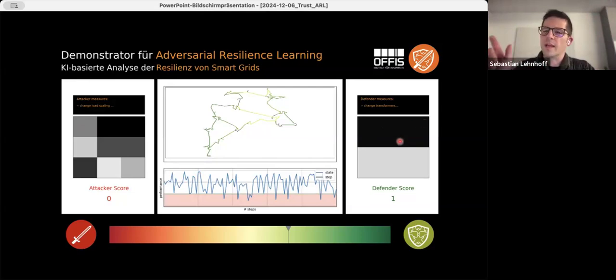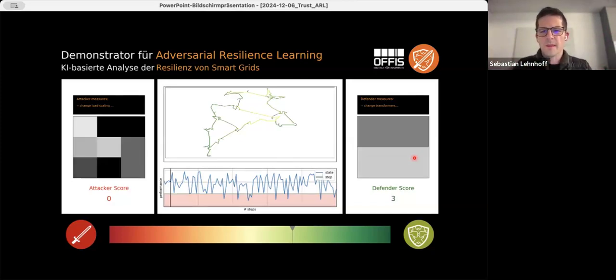And on the right side we now have a transformer, or actually 2 transformers - that's why we only have 2 squares here. The same thing, the tap changer, is basically the transformer. You can imagine tapping up increases the voltage, tapping down decreases it, but on a much larger scale with a much longer lever. So typically you try to counter the synchronization with these tap changers.